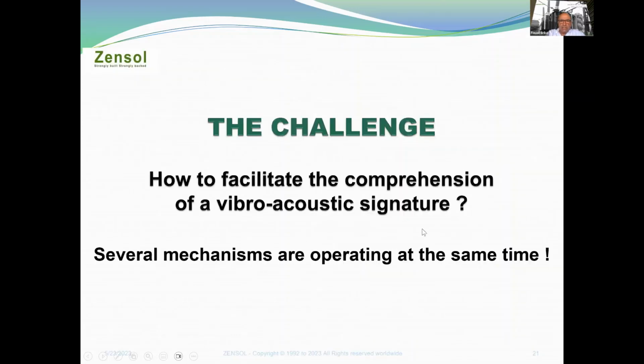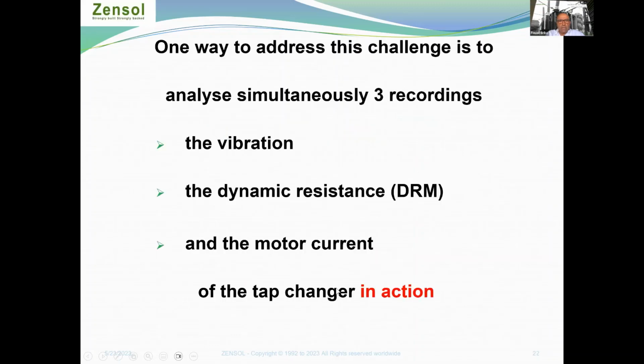So the challenge is how to facilitate the comprehension of the vibro-acoustic signature, since several mechanisms are operating at the same time. One way to address this challenge is to analyze simultaneously three recordings: the vibration, the dynamic resistance, and the motor current of the tap changer in action.